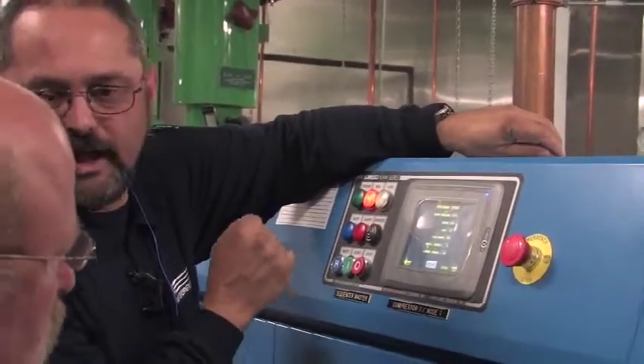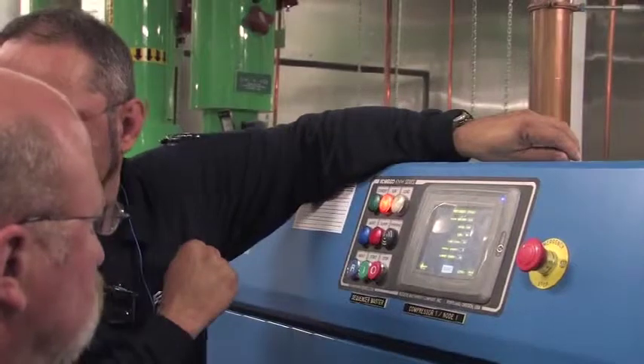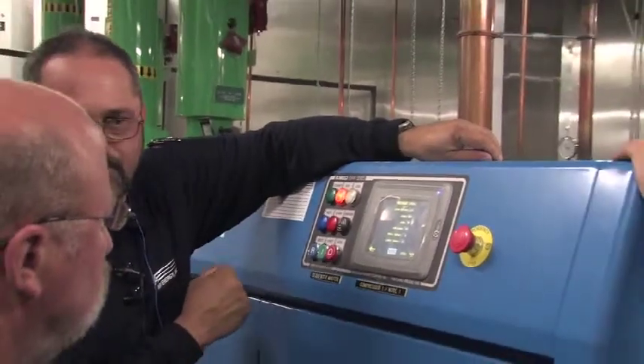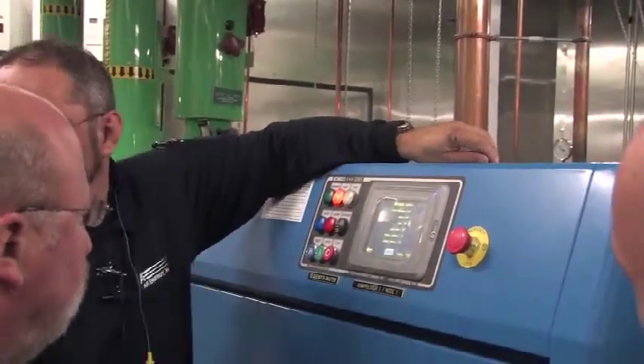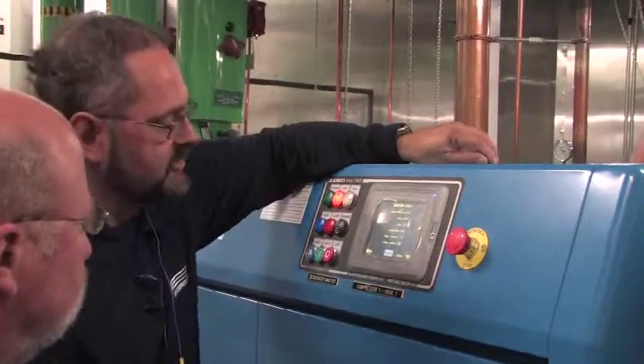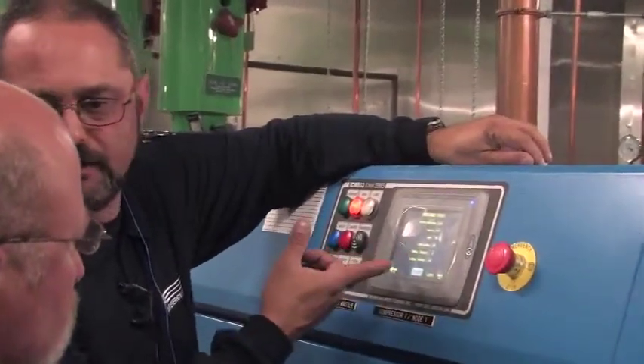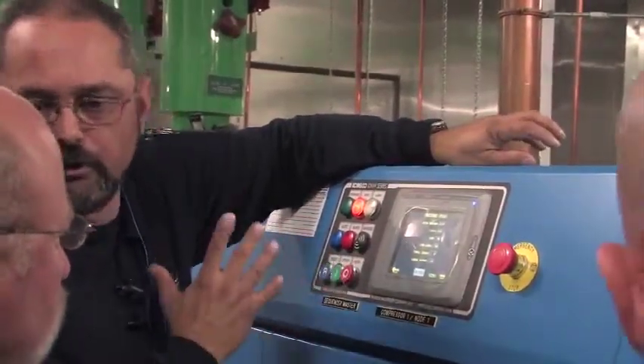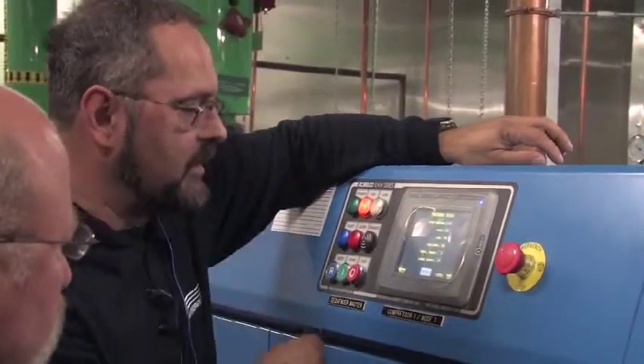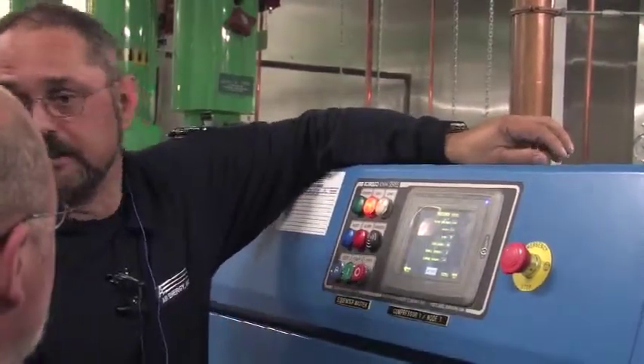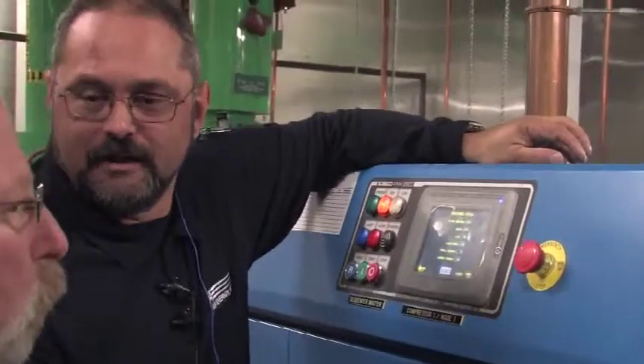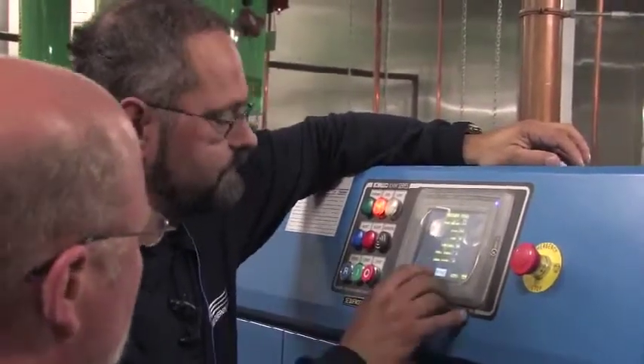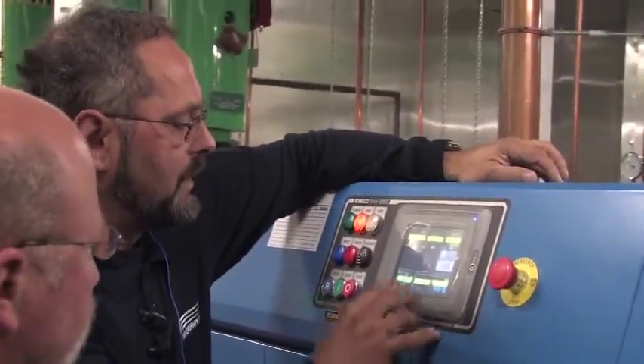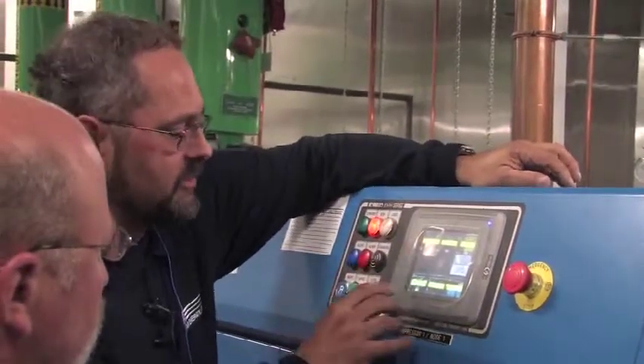But that meant every time I had a float drain blow off and the pressure changed in the header by 3 pounds, everything went nuts. So we might actually end up wanting to make that bigger. We don't know yet. Obviously you don't want to set it so big it doesn't come on when you need it, but you want to set it big enough that it doesn't. You don't know what every application you have drains. But that's where everything is to do with the sequencer.